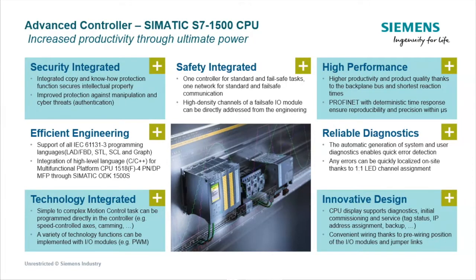Like I mentioned before, it has the display on the front of the CPU. As for some of you that don't know, the S7-1200 does not. This supports a lot of things, but to name a couple of features, it supports diagnostics and the initial commissioning and service like tag status, IP address assignment, backing up the control program. There's a lot you can do right from the display of the CPU. And also, when you talk about diagnostics, it's also very good as far as the LEDs on the CPU and the modules associated. The ET200 MP style modules, which you can see here kind of in this area.